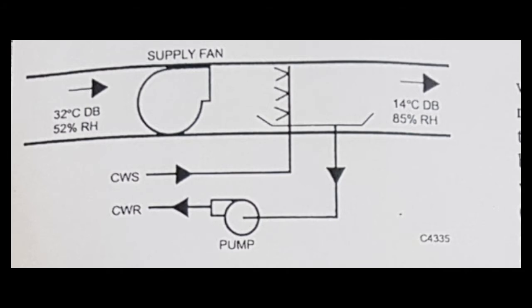The efficiency of the washer is determined by the number and effectiveness of the spray nozzles used and the speed at which the air flows through the system. The longer the air is in contact with the water spray, the more moisture the spray condenses from the air.